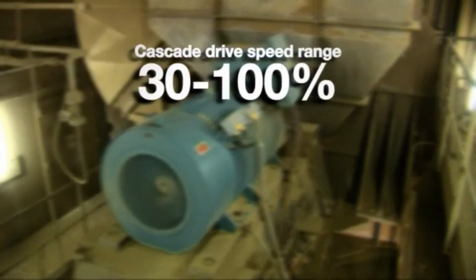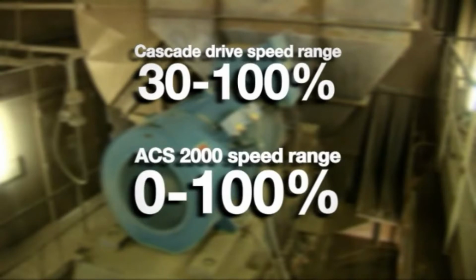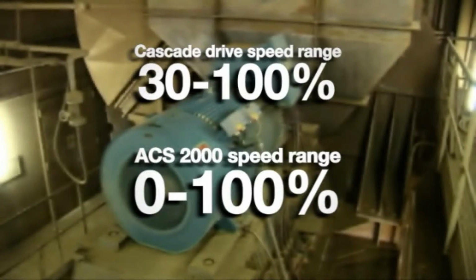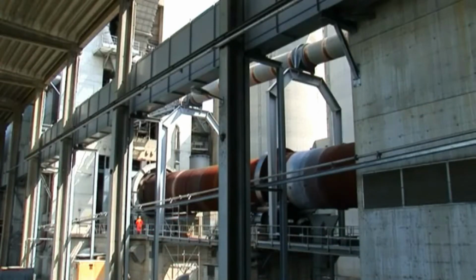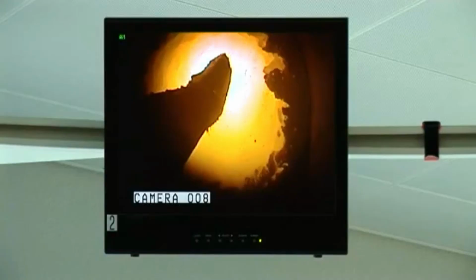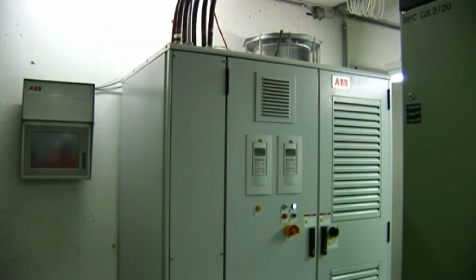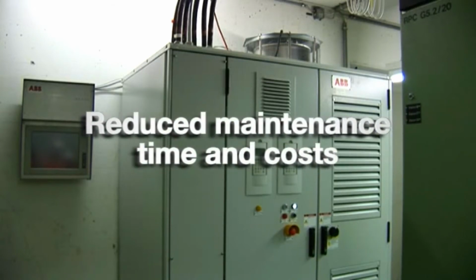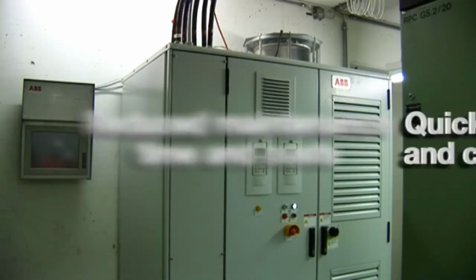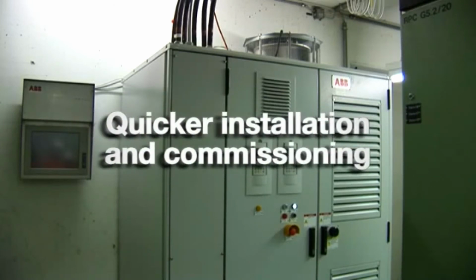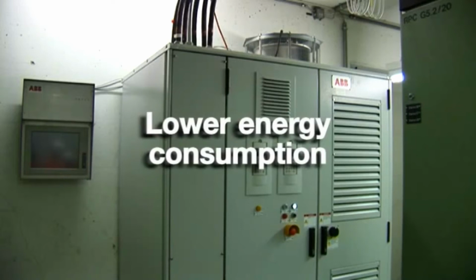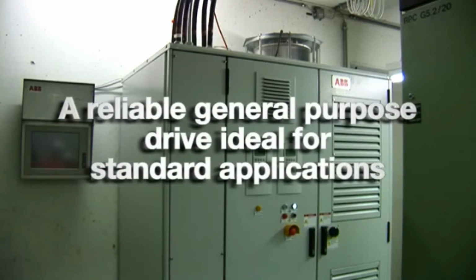Compared to the limited speed range of the Cascade drive, from 30 to 100%, the ACS 2000 offers a wider speed range, from 0 to 100%, resulting in a better process control. The wider range of speed control gives Jura a higher overall efficiency, as it now has greater control over the entire process. So there you have it. One of the first ACS 2000s to be installed is already proving its pedigree by bringing reduced maintenance time and costs, quicker installation and commissioning, lower energy consumption, and above all, a reliable general-purpose drive ideal for standard applications.